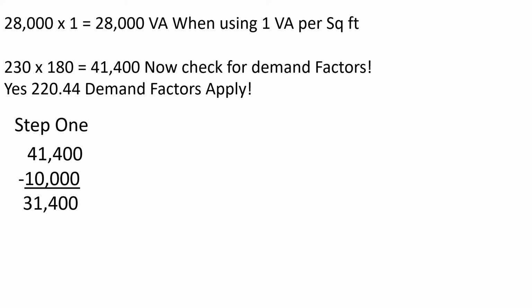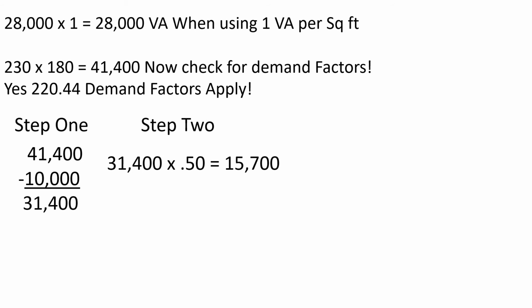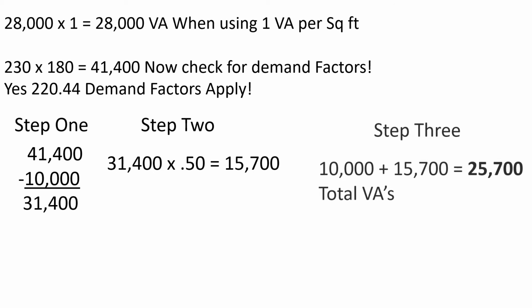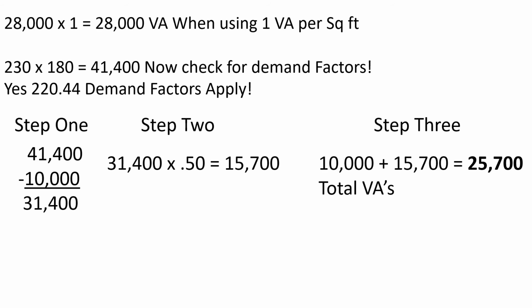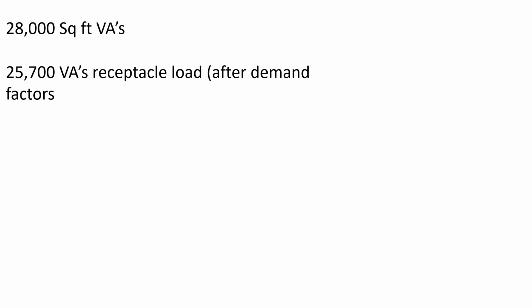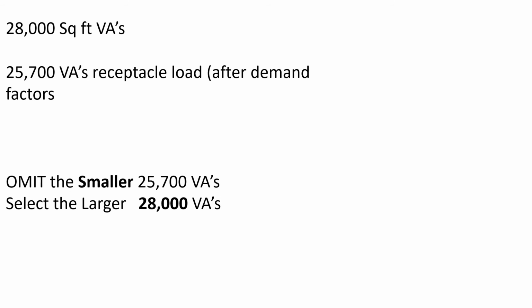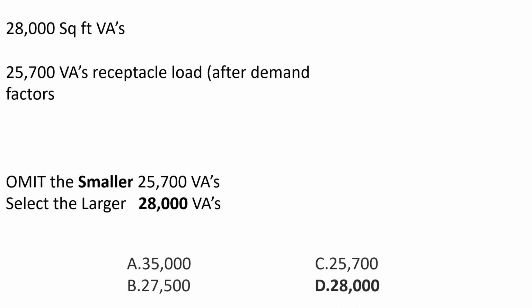Step 1, we take our 41,400 and subtract the 10,000, which sets it aside. That is going to leave us with 31,400. Then all we have to do is take our remaining balance and multiply it by the demand factor, which is 0.50. That is going to equal 15,700. Then we add back the 10,000 that we set aside, and that gives us 25,700 total VAs. Now we have to select the larger of the two. In this case, we're going to omit the smaller, which is the receptacle load, and select the larger, which is the square foot load. And we select D.